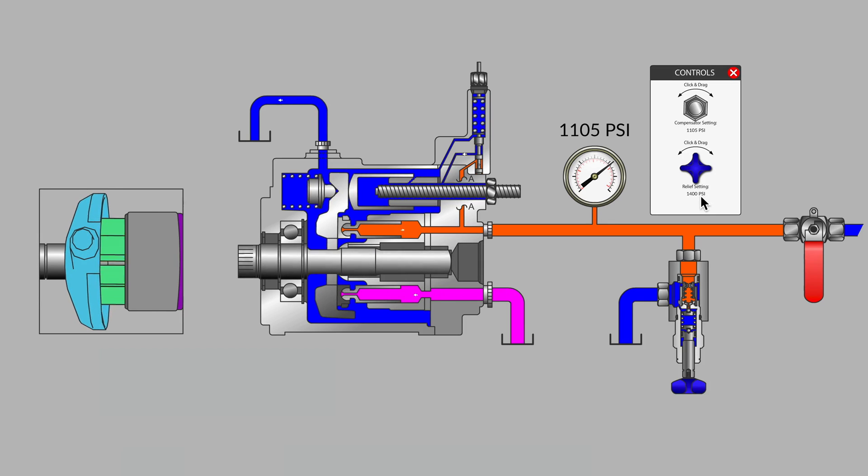Some hydraulic systems set that relief valve only 150 psi higher than the pressure compensator. It is always best to check your machinery manual and find out what the manufacturer recommends for the settings on your hydraulic system.